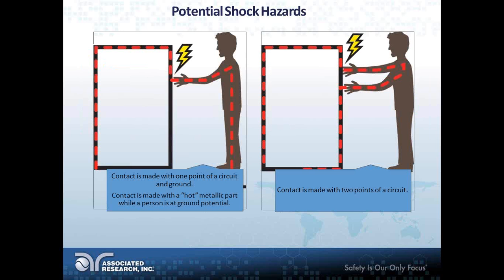You don't necessarily have to be at ground potential for this to happen either. On the right-hand side, that's contact made with two hot points of a circuit. Even if you're not at ground potential, if hand-to-hand resistance is lower than the path the current was going to take through the device, it's going to go through you. That's one of the worst case scenarios, because that means current is going through your chest cavity, which is bad news. So those are some potential hazards—the takeaway is that current will go anywhere it can find a low resistance path, whether that's you, a circuit, or whatever the case is.